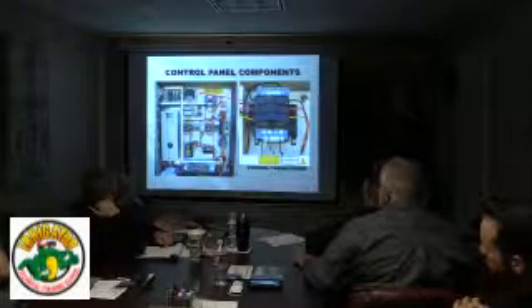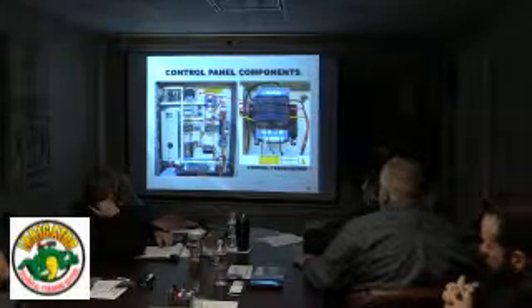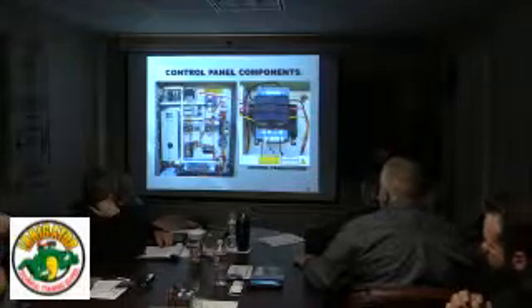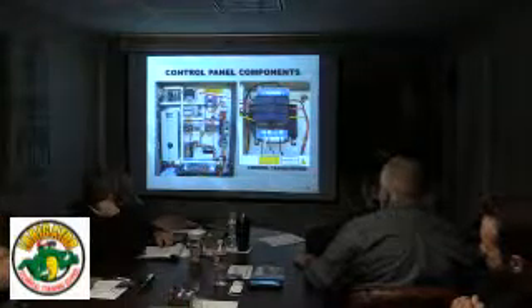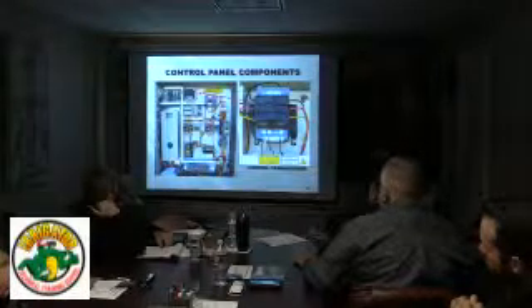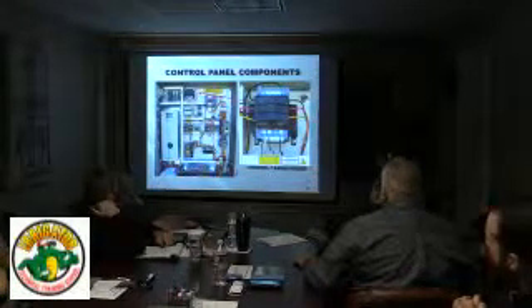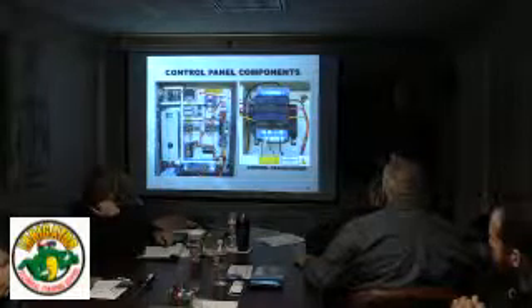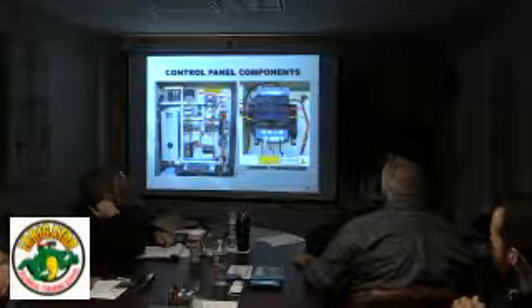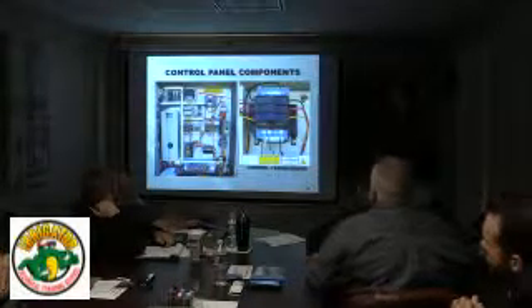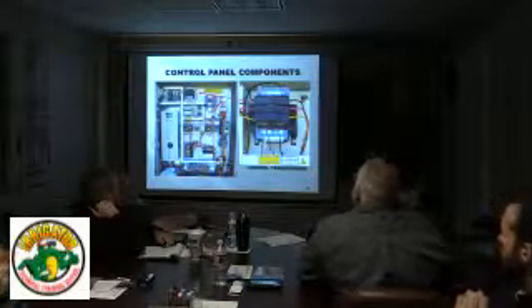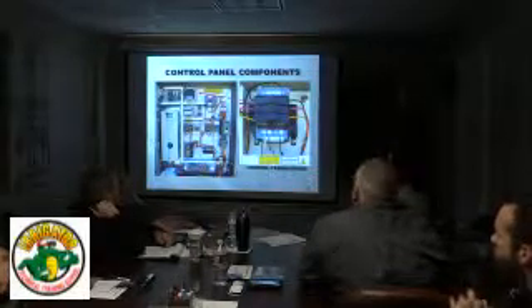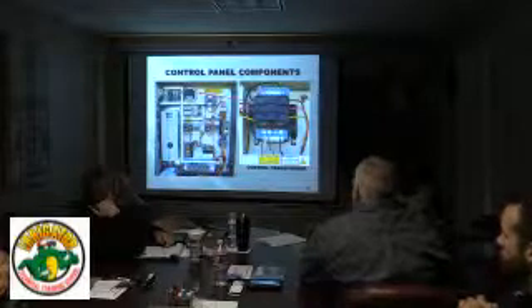on the motor saver. So what we do with this is we get 120 off your neutral and hot here, and we also have a 24 volt AC tap right here. Notice it's purple. If you look at our schematic, the wire for 24 AC on our schematic is also purple. So we try to make it as easy as we can to help troubleshoot these and follow wiring and stuff as much as we can.